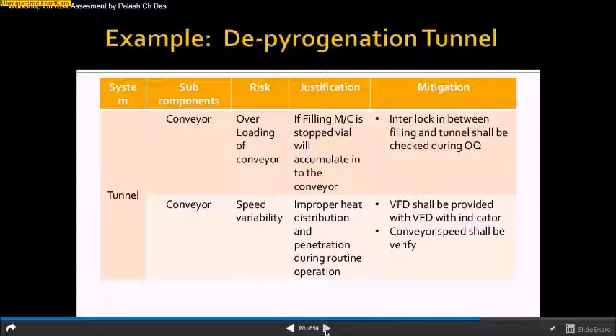Then conveyor speed variability. Improper heat distribution and penetration during operation. If there is speed variability, we need a VFD, a variable frequency drive, provided with an indicator, and the speed of the conveyor shall be challenged and verified during your qualification, and PMP shall be done. So this is the scenario I am discussing based on my knowledge and some examples. You need to put your knowledge and more effort into this.